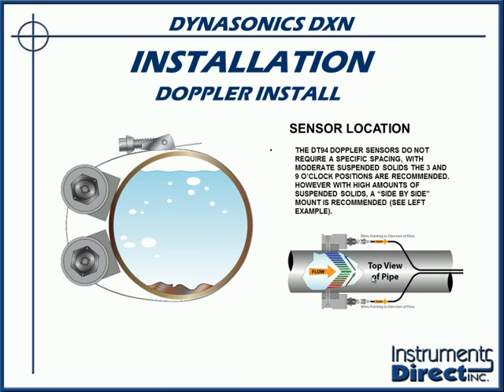Now, an ultrasonic Doppler transducer does not have a specific spacing requirement. Traditional applications are, the cleaner the liquid, we mount it transversely across the pipe at 9 and 3 o'clock. And should you have an application with a tremendous level of solids, your sludges and your slurries and your mining applications, and you lose your signal, then you need to move the transducers side by side. Again, traditionally on the side of the pipe. Vertical really doesn't make any difference.